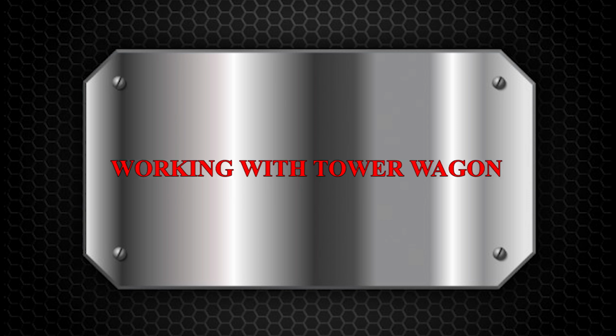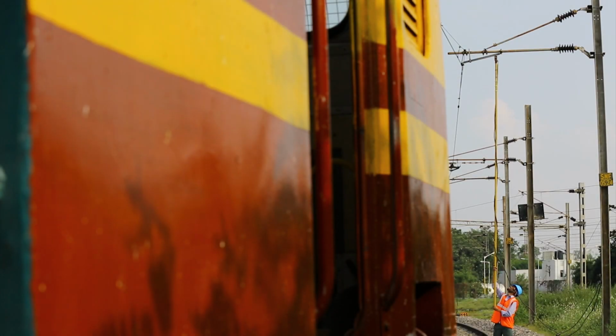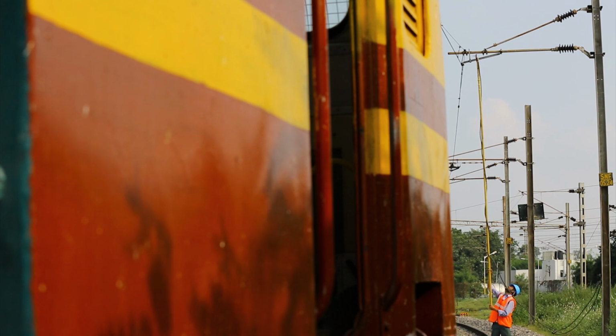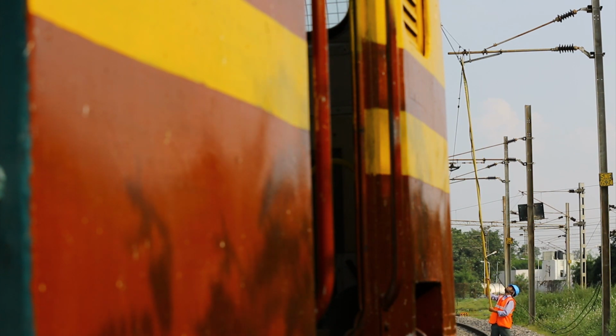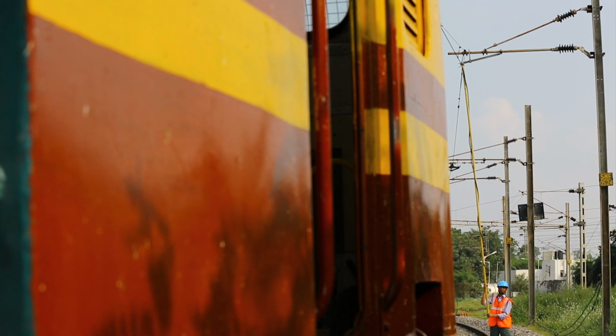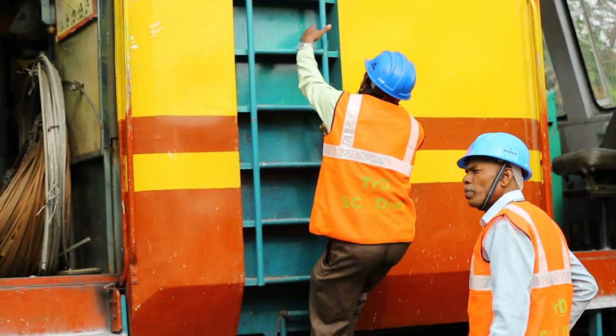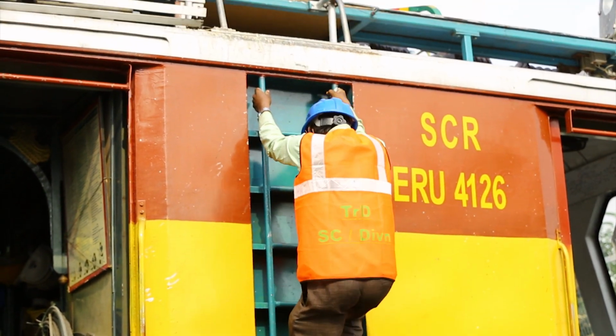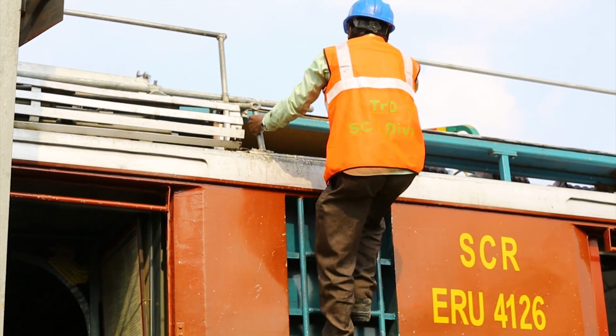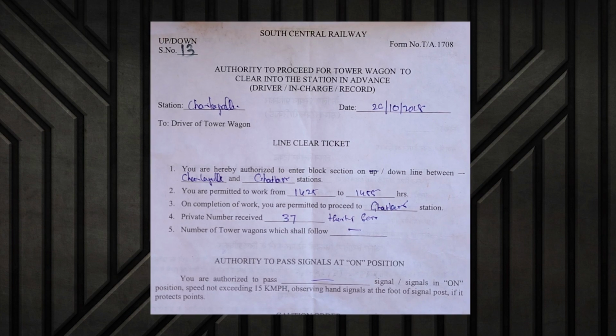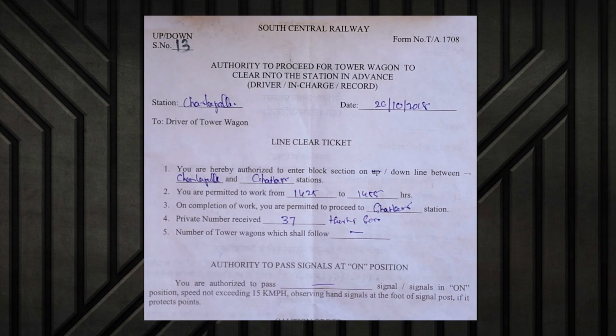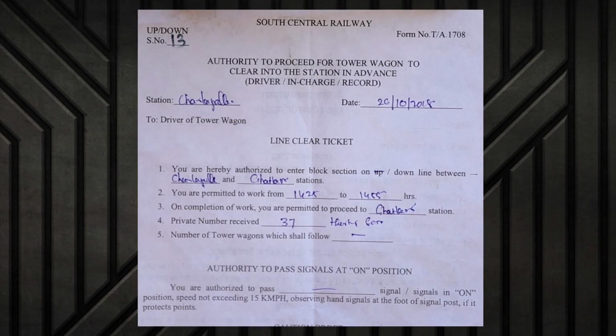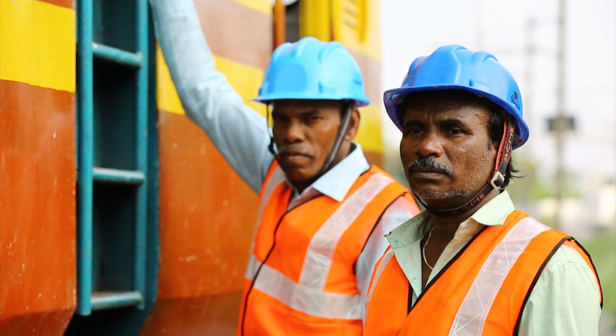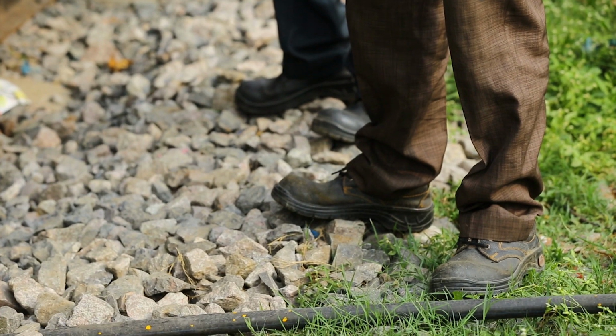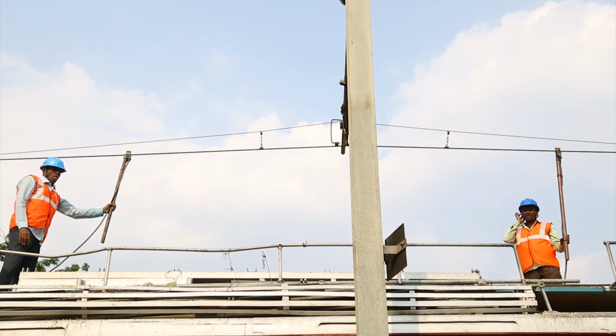Working with tower wagon. After obtaining permit to work, that is PTW, ensure power supply of concerned elementary section is switched off and OHE earthed before commencing the work. Climb on roof of tower wagon only after obtaining permit to work PTW from TPC. If traffic block is taken, ensure that written memo or authority has been taken from concerned ASM on duty. Always use industrial helmet and shoes during work at tower wagon. 2 discharge rods must be provided on both ends of contact wire of working personnel.